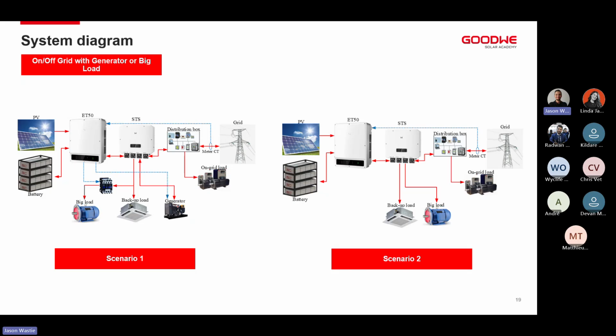Where we could use this is, for example, a packaging facility where small packaging machines or something similar run as so-called big loads, and just the office lights, server, printer, that kind of thing run as your standard backup loads. When my batteries are full, or during peak production times, allow both big load and backup loads to be closed. When my batteries reach 40%, open that relay and disconnect my big loads, meaning the physical production will stop. However, I'll still have full access to my normal office equipment.